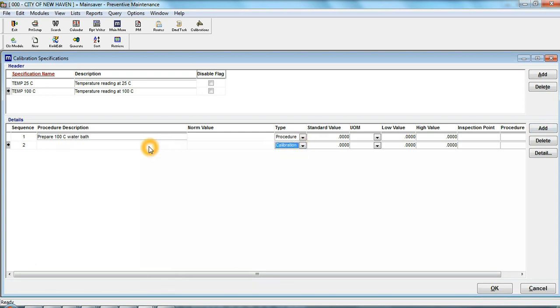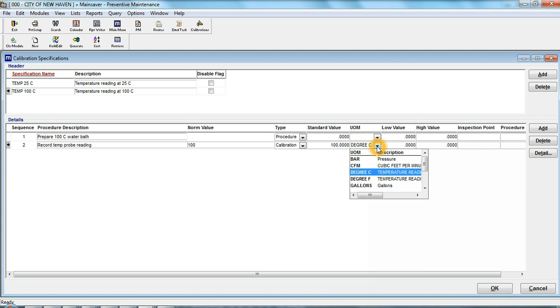Now I'll add the calibration. This is the actual value. Record temp probe reading. And normally this is going to be 100. The standard value is 100. The unit of measure is degrees C. Units of measure are set up in System Admin if you don't see the ones that come with Mainsaver. And let's say that a low acceptable value is 99 and a high value is 101.